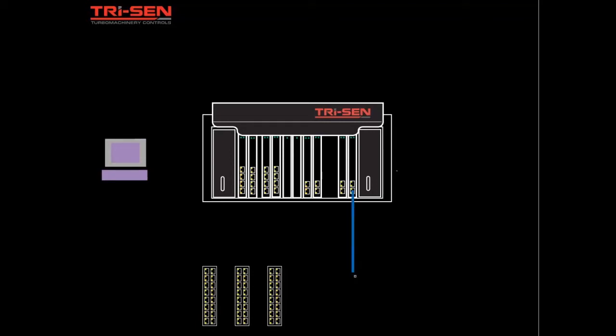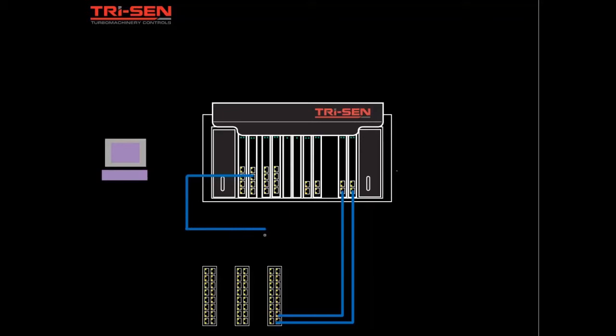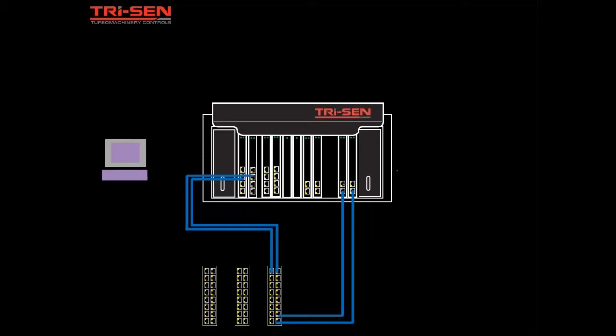We've dropped in three network switches down at the bottom and the first network we're going to draw in is what's called the interlink. That's the only network that we see two of on the chassis processors. It goes to the J3 connections on the node processors and that's the only place you'll see these blue networks is for this interlink.